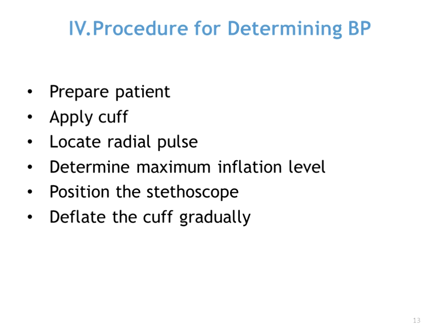You select the cuff size, you apply the completely deflated cuff on the patient's arm, support it at the level of the heart, and if the arm rests on the arm of the dental chair higher than the heart, again, it's going to be different than if it's directly at heart level. You place a portion of the cuff that contains the inflatable bladder directly over the brachial artery. And the cuff that we have has an arrow that lets you know where that brachial artery is, as far as this is where you place the cuff.